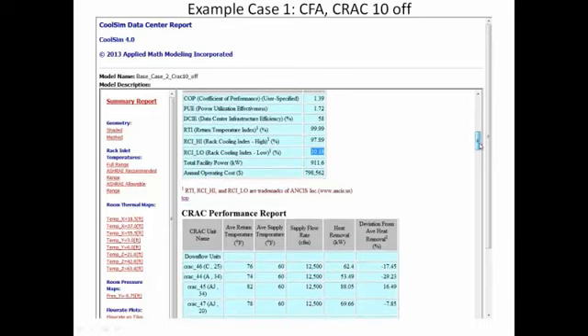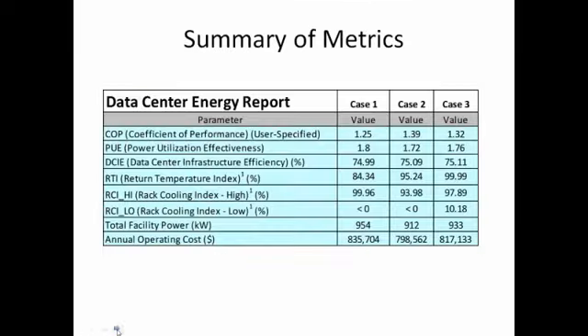So what I did here is I put the plots side by side so you could see them. Now, here in case 1, the PUE actually went down. In case 2, to 1.72, and then went up a little bit here to 1.76. And that's because of the different cooling unit things that we're shutting off.